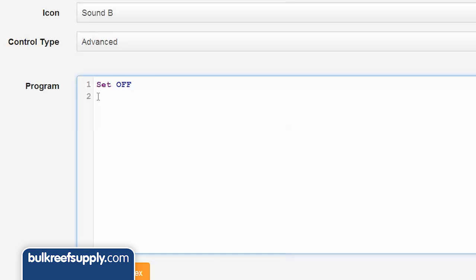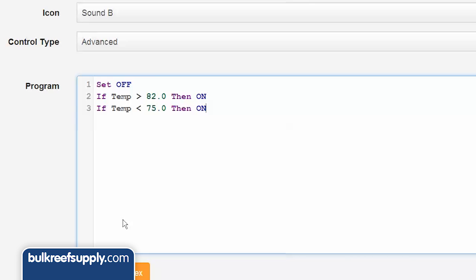The first alarm is typically related to temperature. Something like: if temp greater than 82 then on; if temp less than 75 then on. This will set off an alarm if the temp ever goes over 82 or below 75.